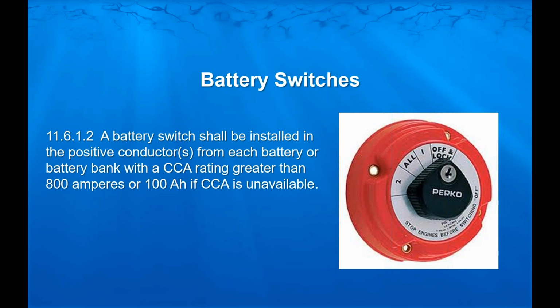Now, 800 amp hours is not a lot, and 800 amps is not a lot. You can get maybe a group 24 battery that does not have 800 amps, but you can get group 24s that have 800. And if you go to a group 27, group 31, you're definitely going to be higher than 800 amps. So in most all cases, you're going to be required to have a battery switch, a main disconnect in that DC circuit. And even if it's not required, if it's possible, it's a very good idea, especially for servicing considerations, not to mention safety considerations.